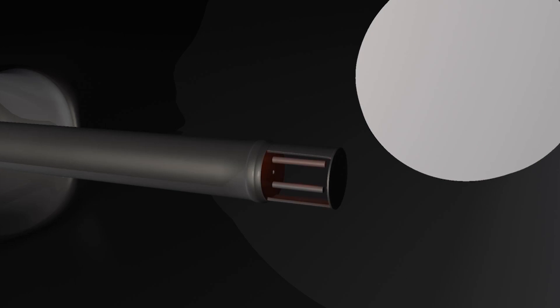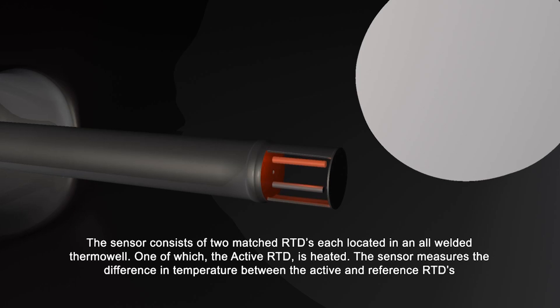The sensor consists of two matched RTDs, each located in an all welded thermowell, one of which, the active RTD, is heated. The sensor measures the difference in temperature between the active and reference RTDs.